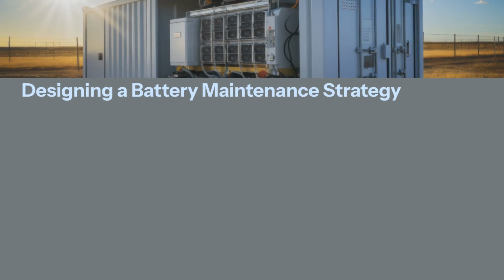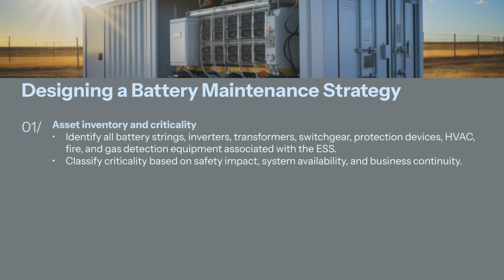Let's look at how to design a battery maintenance strategy. A battery energy storage system specific electrical maintenance program aligned with NFPA 70B should, at a minimum, cover first, asset inventory and criticality. Identify all battery strings, inverters, transformers, switchgear, protection devices, HVAC, fire and gas detection equipment associated with the energy storage system. Classify criticality based on safety impact, system availability, and business continuity.